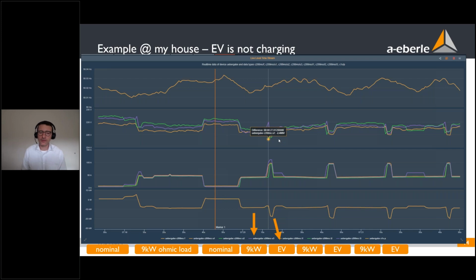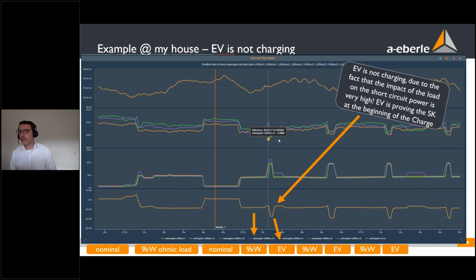What happens then? I'm charging, I want to charge my EV here, and the EV is not charged in this situation, because the impact of the load on the short circuit power is very high. The EV has to probe the grid a little bit, and it probes at the first moment when the charging process starts. The short circuit power is not big enough, so the charging stops directly.